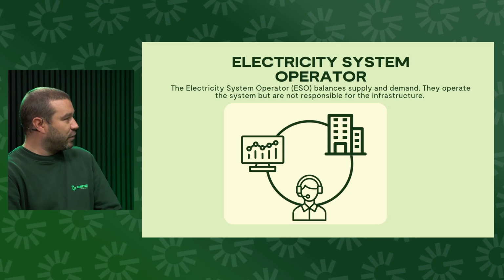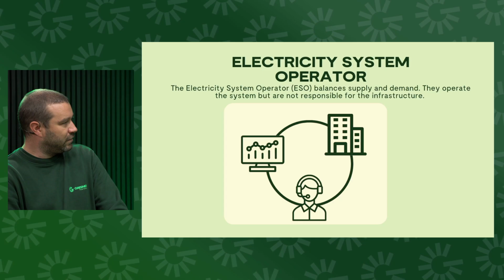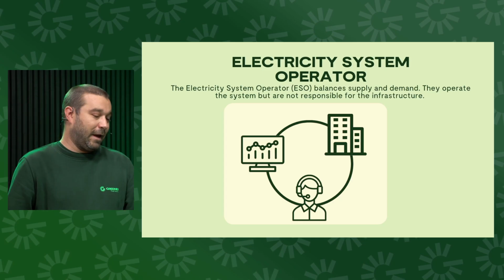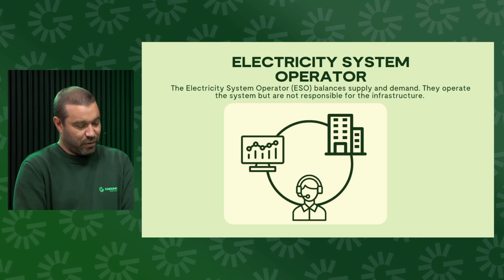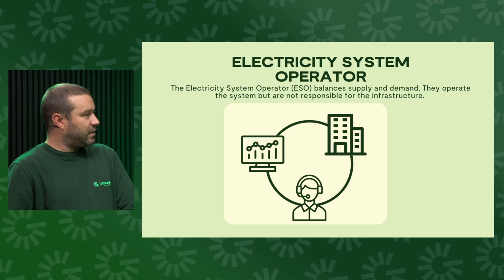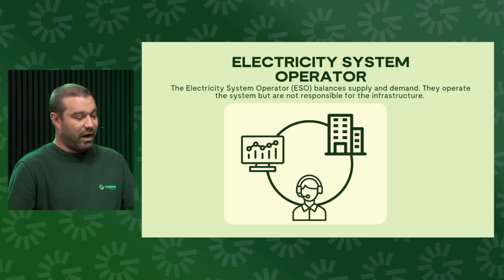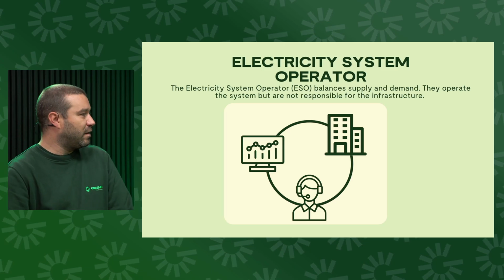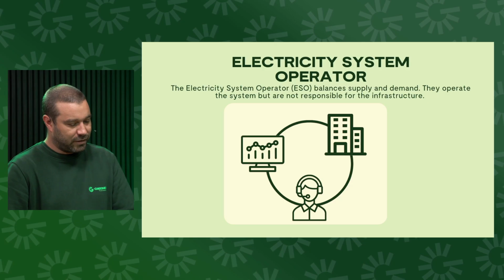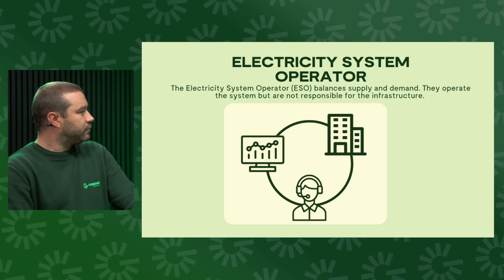The frequency tolerance on the grid is about 0.2 hertz either side, up or down, and that's the job of the ESO. But we also use this frequency in battery systems to control microgrids and power flow across a network. It's the same principle in the grid as in a microgrid, except for the scale. If there's too much energy, the frequency will be high, and if there's not enough, the frequency will be low, so you have to adjust accordingly.